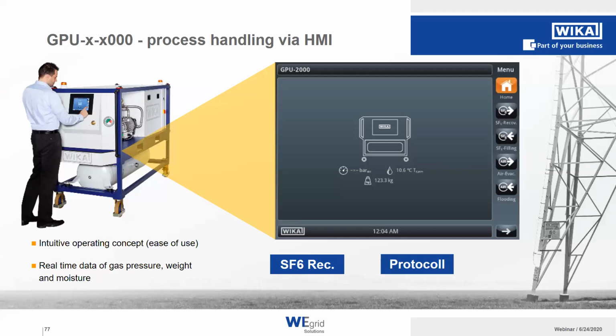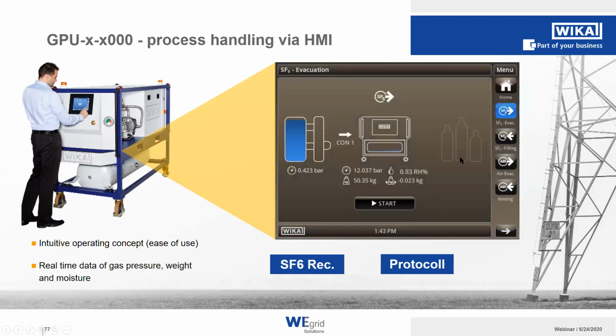As with the GPU, we have an HMI where you can start all the processes. For example, the home screen looks like that. We have our unit, we have the pressure, we have the weight of the gas inside our tank, we have the dew point temperature of the gas, and okay, here is no pressure shown at the moment, but you will get that information when you start the process. All our processes are listed on the right side: SF6 recovery, SF6 filling, air evacuation and air flooding. And if we like to start a process, for example, it looks like that.